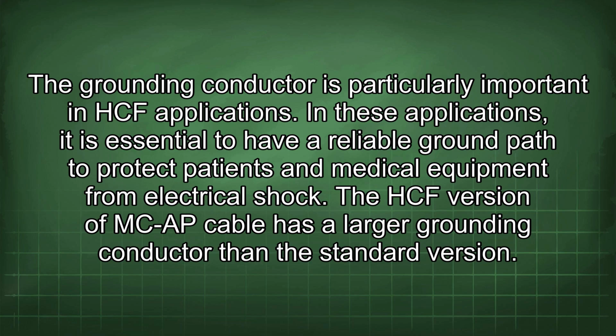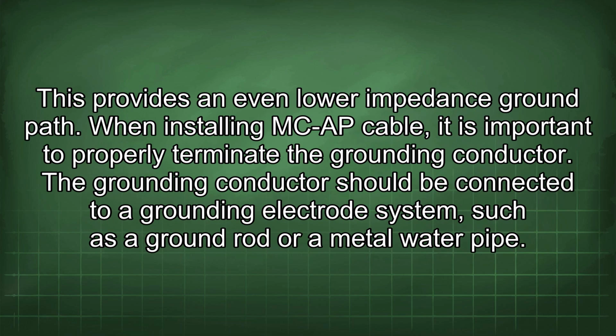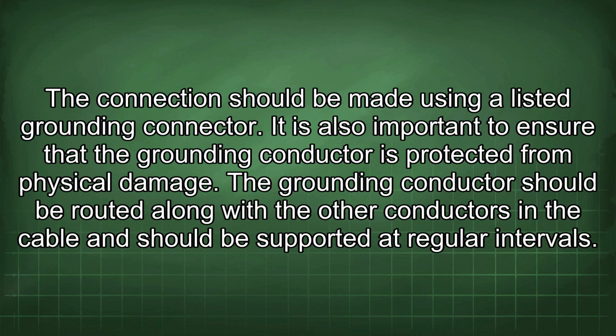The HCF version of MCAP cable has a larger grounding conductor than the standard version. This provides an even lower impedance ground path. When installing MCAP cable, it is important to properly terminate the grounding conductor. The grounding conductor should be connected to a grounding electrode system, such as a ground rod or a metal water pipe. The connection should be made using a listed grounding connector.